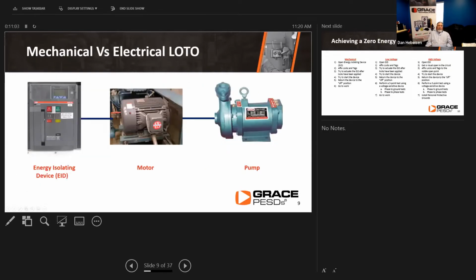So let's talk real quickly about a mechanical versus electrical lockout tagout. And here you see on your screen on the left-hand side, we have the energy isolating device, or the disconnect, or however you want to phrase it. Then you actually have the motor that it's connected to, as well as the pump that the motor is connected to. So let's say, for example, this motor is operating fine, but we do realize that one or two of the bolts at the foot of that motor have actually come loose. So we need to work on that piece of equipment.